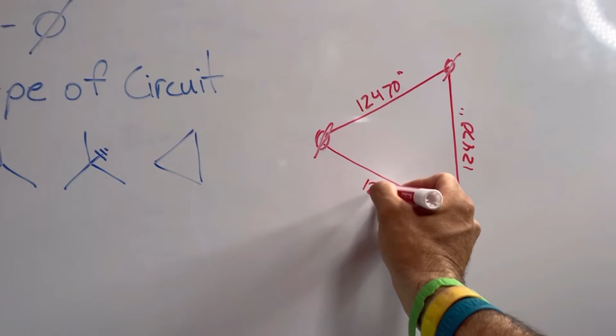So something interesting about delta circuits is we do not have a neutral on a primary delta circuit. And it's going to be very obvious as we go later on through this process, so once you guys get dialed in on vectoring and all that, it becomes very obvious why we don't have neutrals on primary delta circuits. So the only potential that we have to work with in a delta circuit on the primary side is a phase-to-phase potential. That's it. And in this case, that phase-to-phase potential is 12,470 volts.